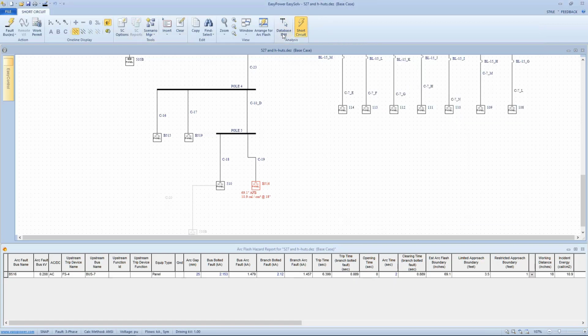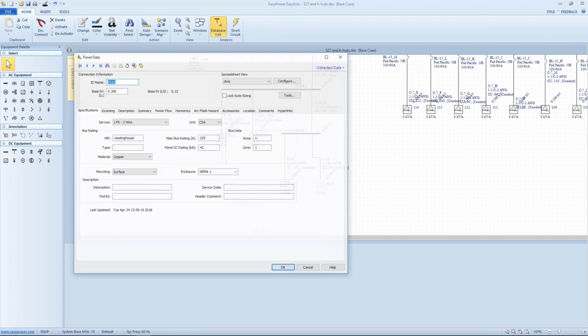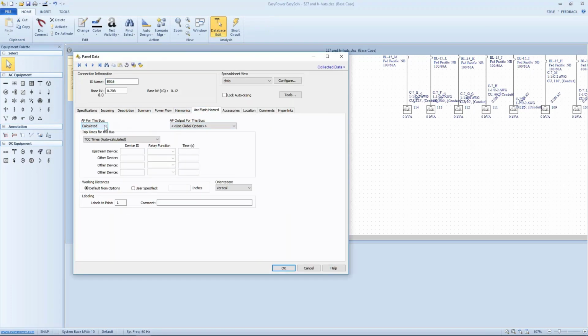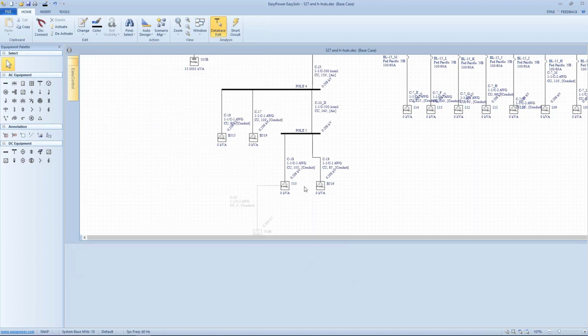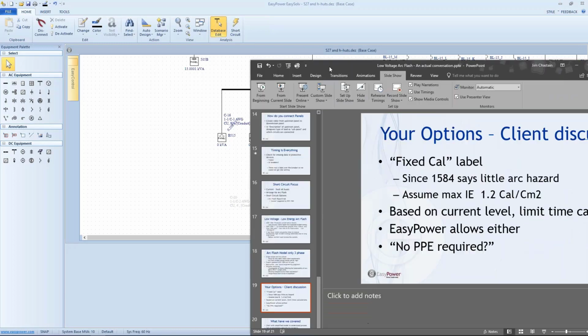Secondly, if I go back to database edit and look at this particular panel, if I go into its arc flash tab, rather than calculate it, I can force it to a specific incident energy. And if we say 1.2 calories and put my arc flash boundary at 18 inches, I might be justified, or the client might agree, based upon what he's trying to do for low voltage panels. So this is where I would do it on a localized basis. Now, again, either one of those I would not do without a serious conversation with the client.